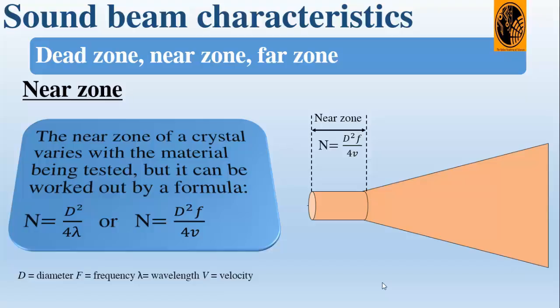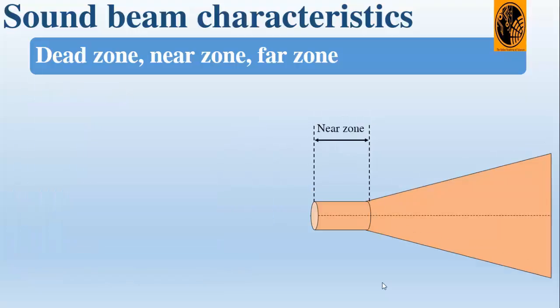D is the diameter of the crystal, F is the frequency, lambda is the wavelength, and V is the velocity of sound propagation.